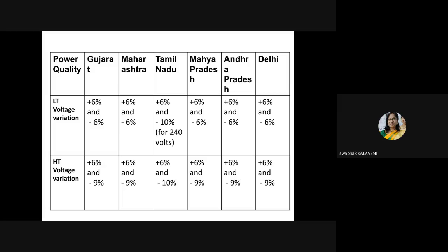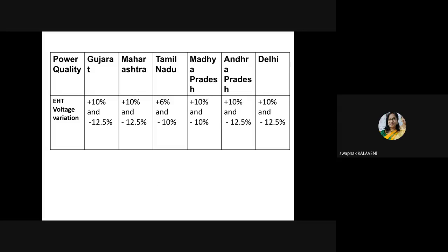For LT voltage variation, in the sense of single phase or three phase, Gujarat is only plus or minus 6%. Maharashtra plus or minus 6%. Tamil Nadu plus 6%, minus 10%. Madhya Pradesh plus or minus 6%. So it is plus or minus 6% at the LT level. The HT level is a different level. Similarly, at the EHT level, it is 10% to 12.5%. That is, throughout the country, it is about plus or minus 10%. In Tamil Nadu, it is plus 6%, minus 10%.